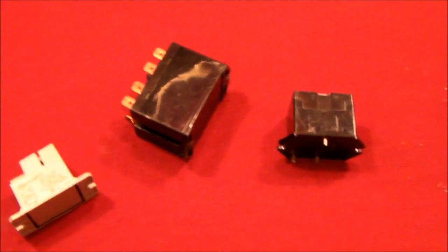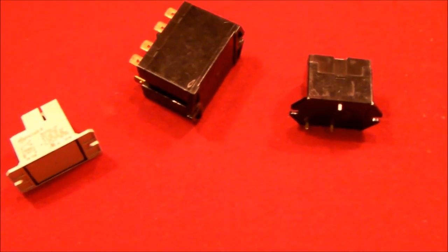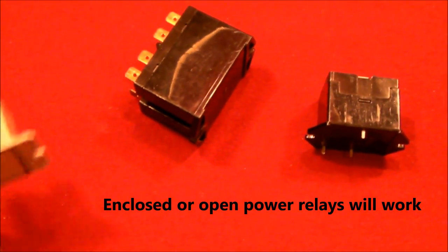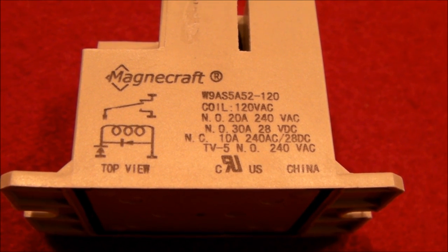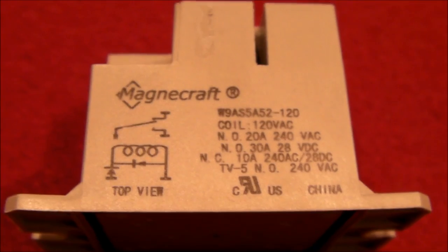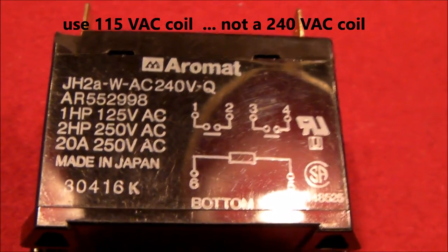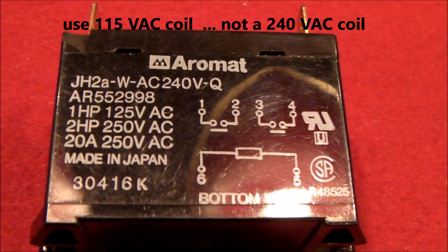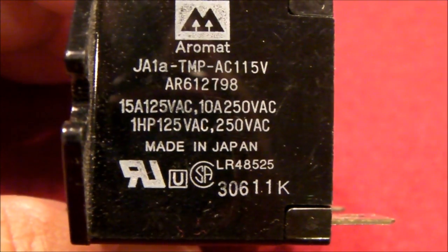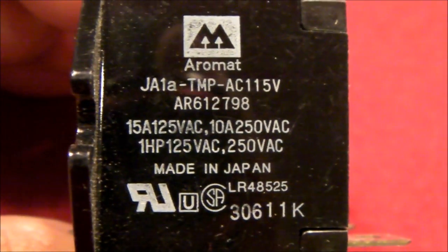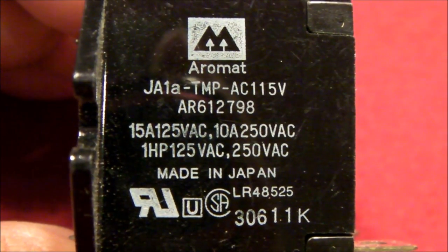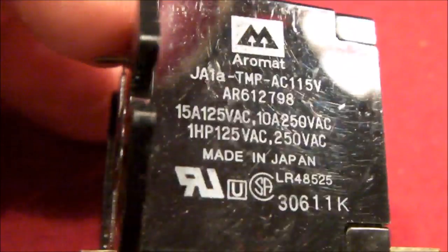The relay that I use on my next installation will most likely be something that looks like one of these enclosed relays. Let me just give you an example here. If you look up this part number, this relay has a one horsepower motor rating or a relay that looks similar to this one with a different coil. You can see this one has a one horsepower at 125 volt AC rating. And this relay right here, you can also see that it is rated 15 amps, but it also has a one horsepower at 125 volt or 250 volt rating. So the horsepower rating is really important on these relays or contactors, whatever you decide you're going to use.